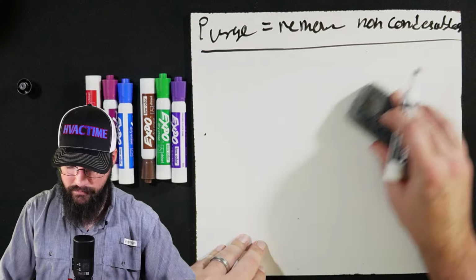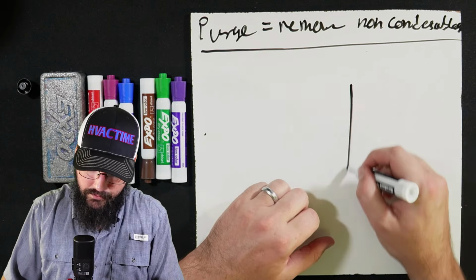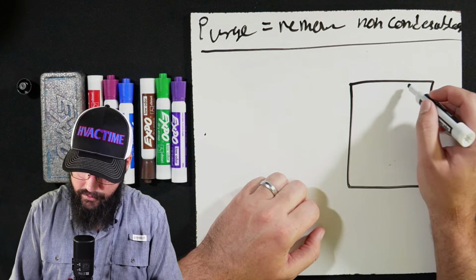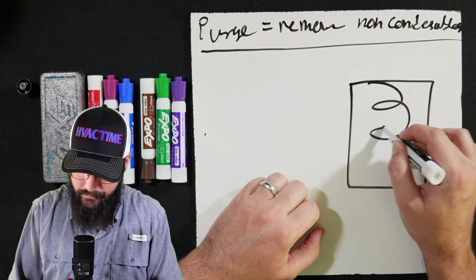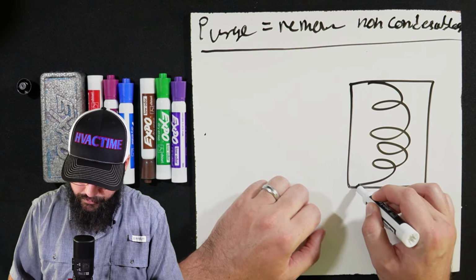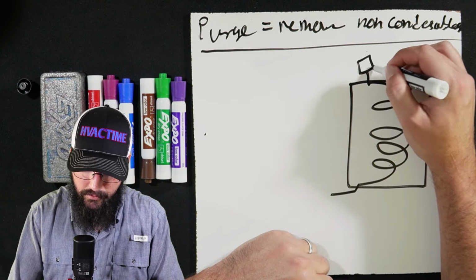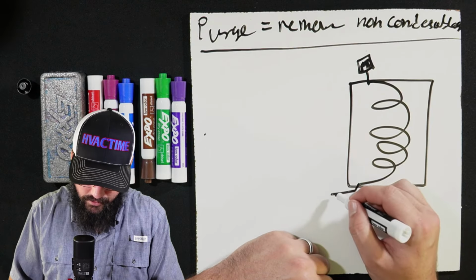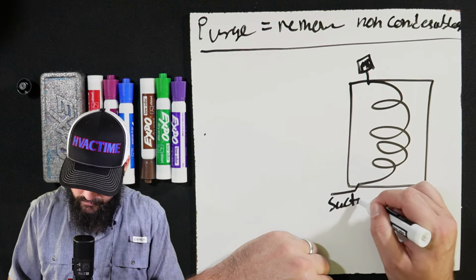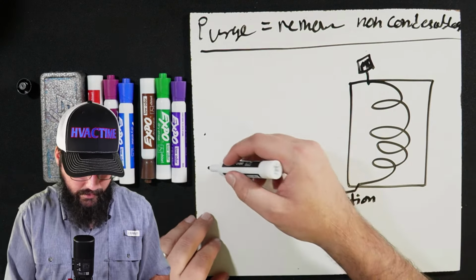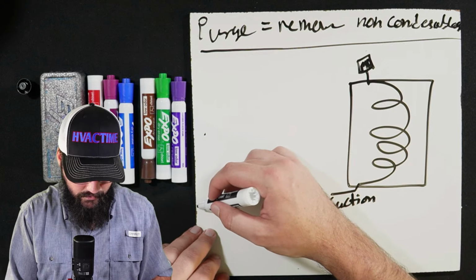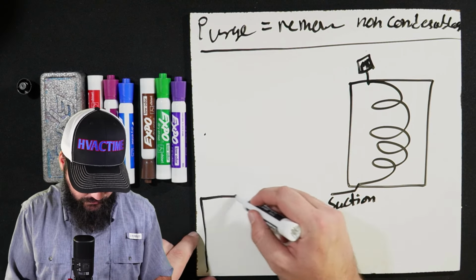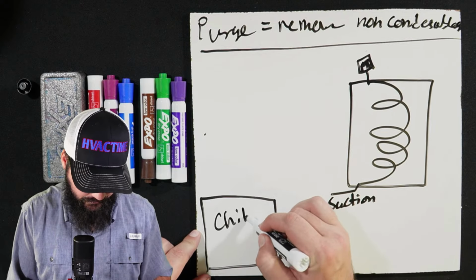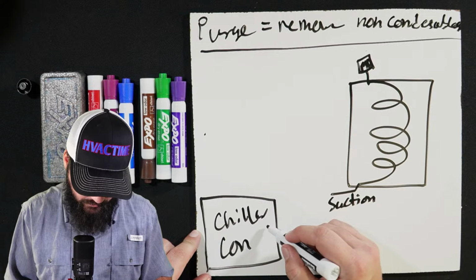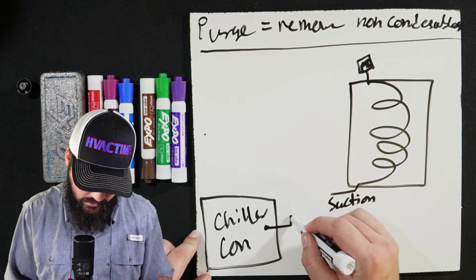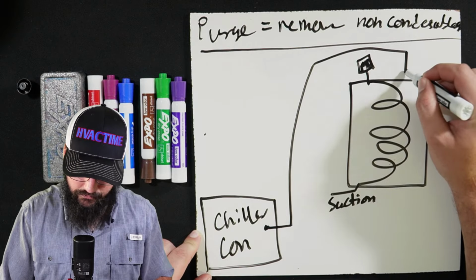but they do interact here in the evaporator. So let's do a blow up of the evaporator itself. So in this evaporator, we have our refrigerant coil coming from our little purge unit system. So this would be your metering device feeding into the top. This would be your suction, okay, coming back into the compressor.